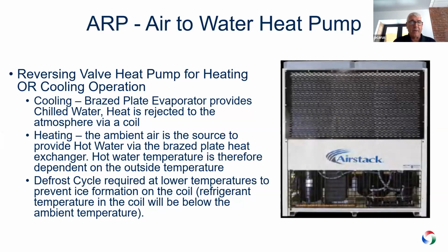The first one we're going to talk about is just a straight air to water heat pump, and it's called an ARP. Has a reversing valve, and it's an either or machine. In the cooling side of the application, there's a brazed plate evaporator that provides the chilled water. Heat goes out through the coil. Now, this machine that you see is an older version. It's just got standard fans on it, but today's versions of this machine have ECM fans on it. They can have a VFD on a standard fan. So the technology has ramped up significantly with this air to water heat pump machine.